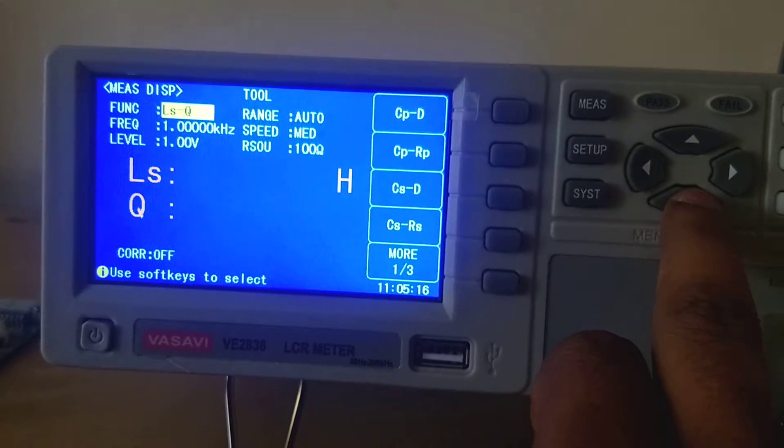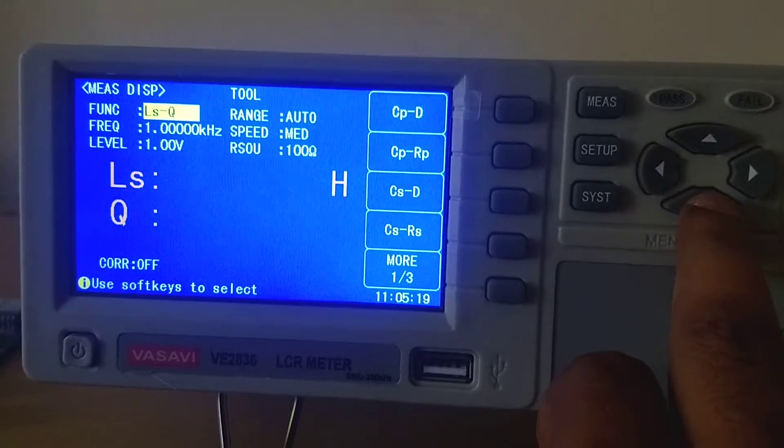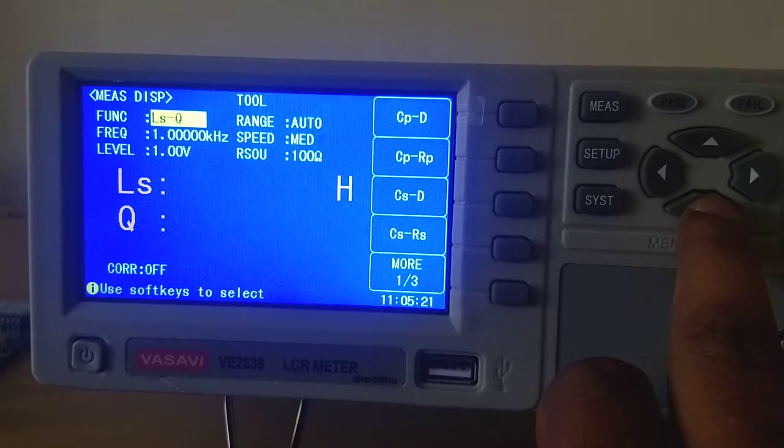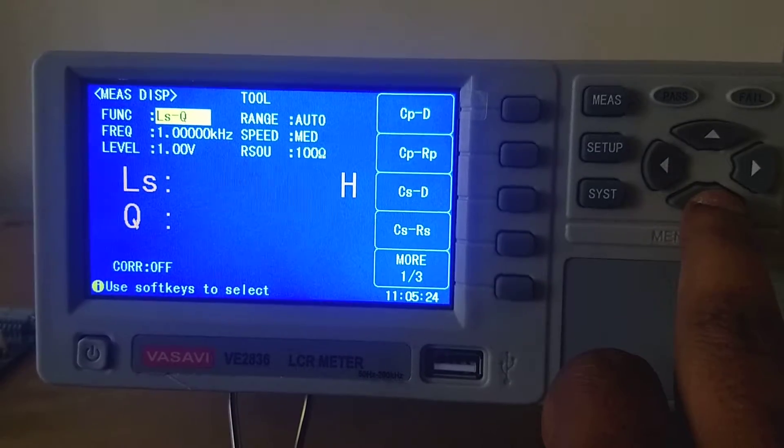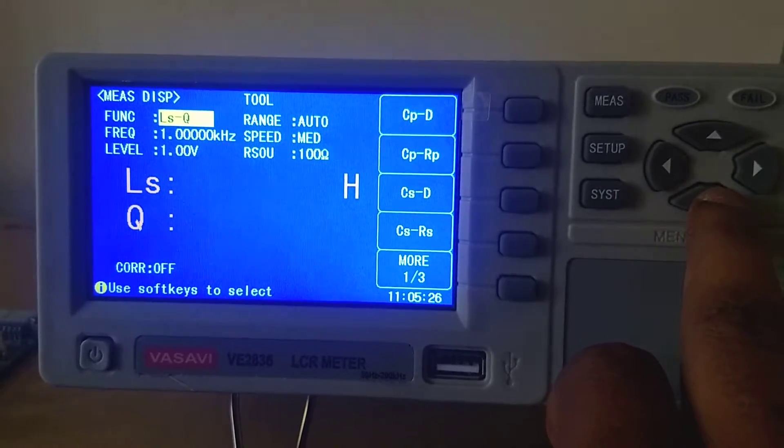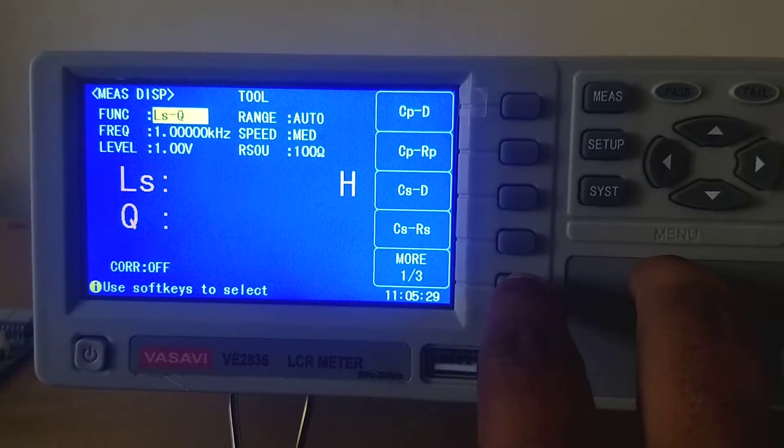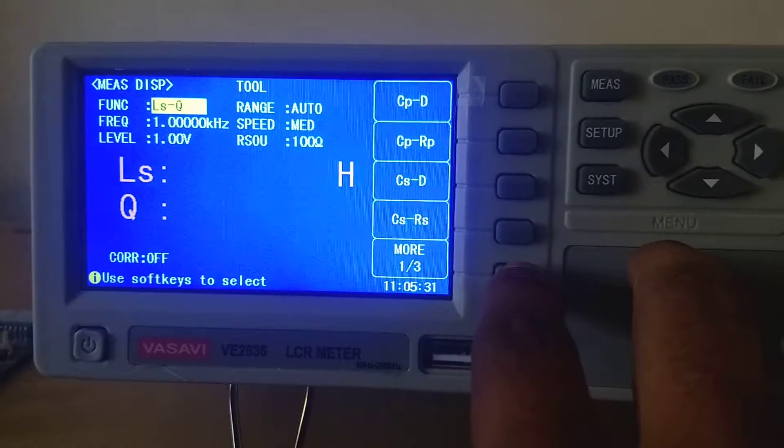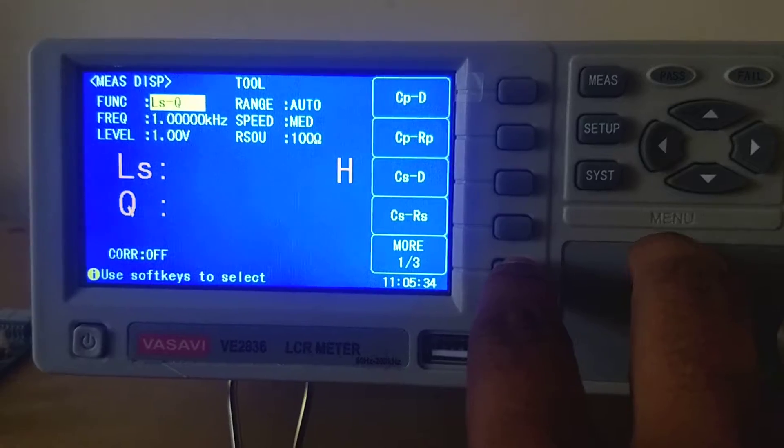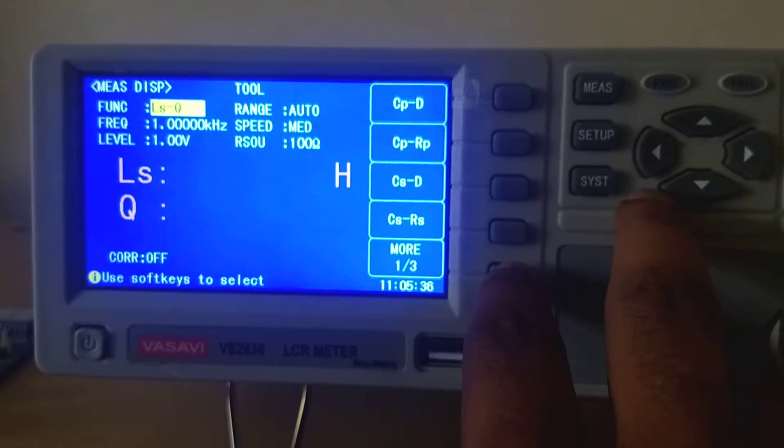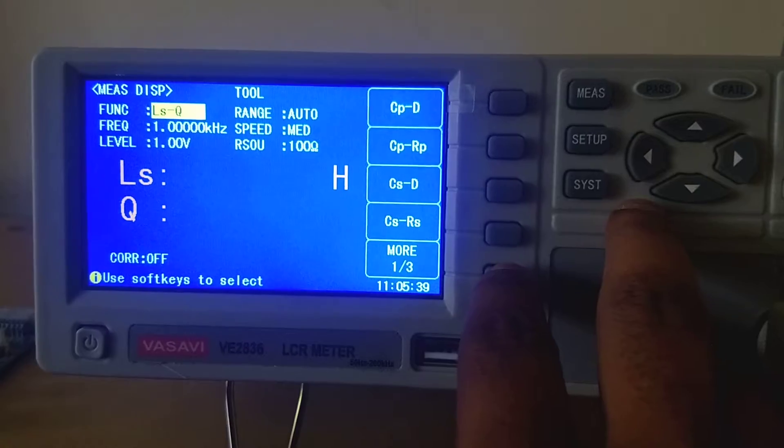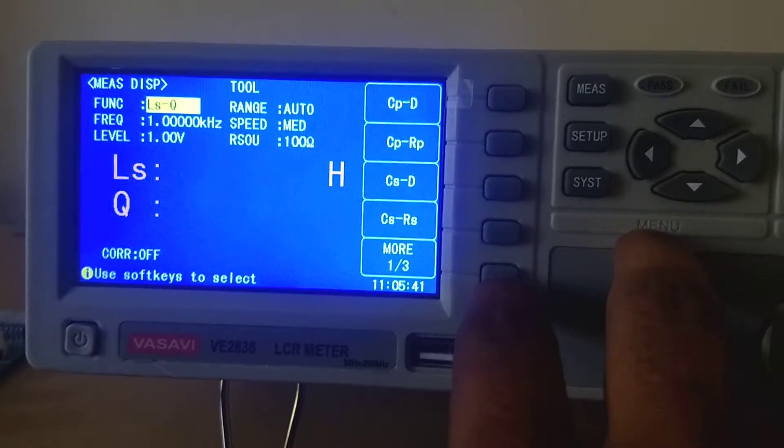Now we will show you how to select function. You can select what parameter you want to test. This LSQ - LS stands for series inductance and Q stands for quality factor. In this same screen, you can get two readings: inductance in series and quality factor. Like this right side, you can select what all parameters you want to select.